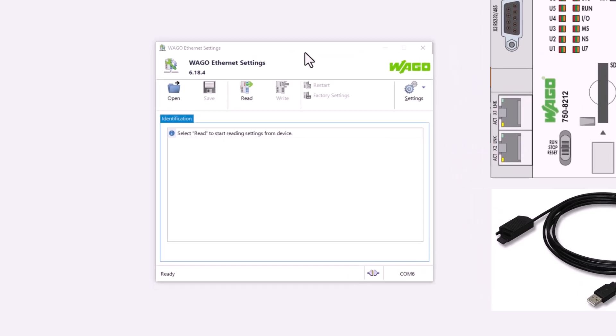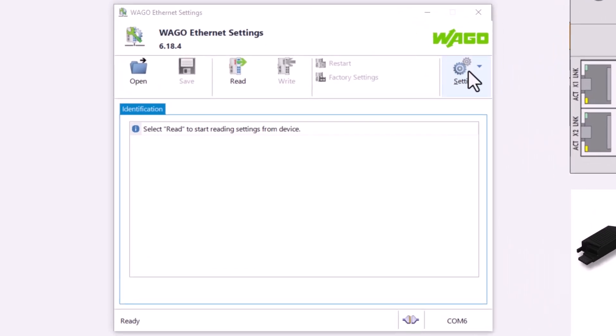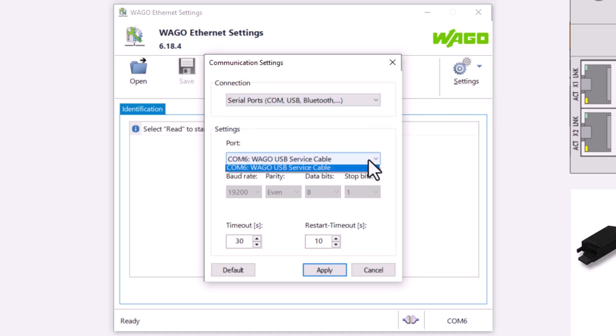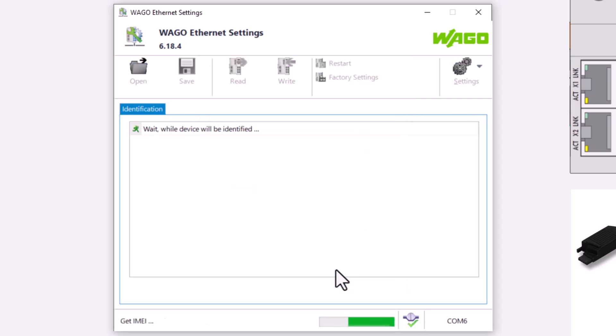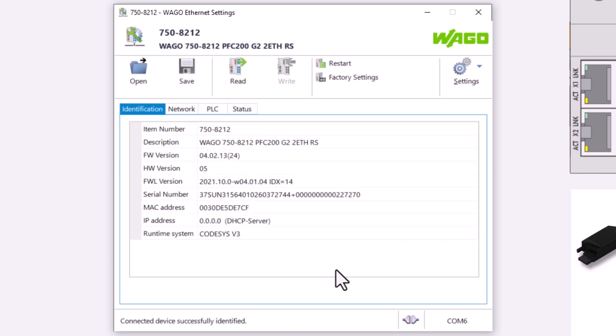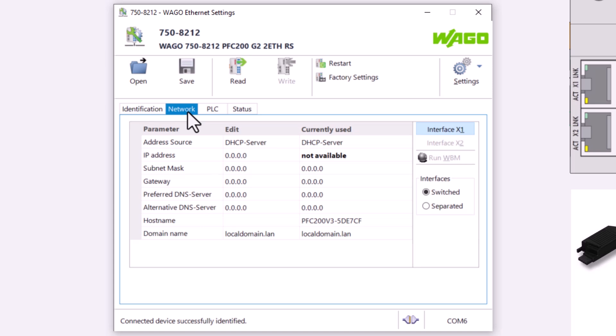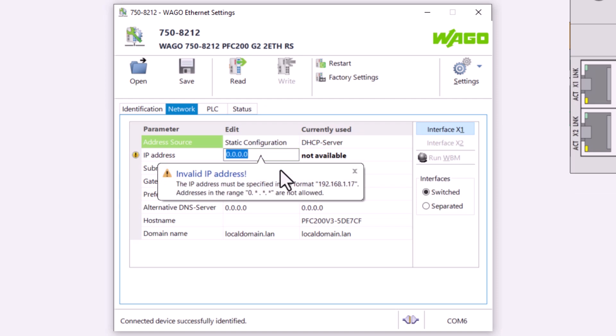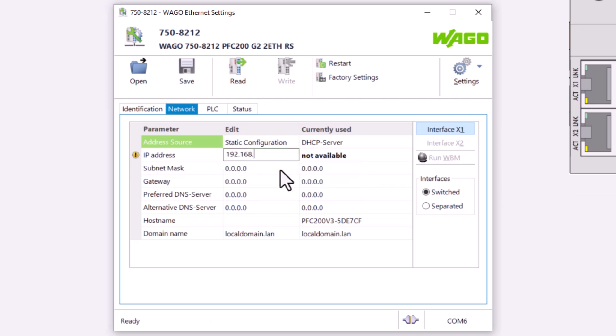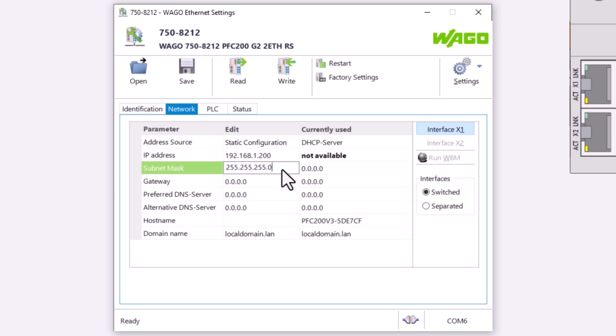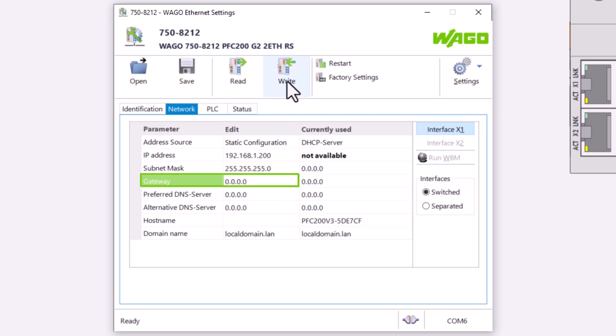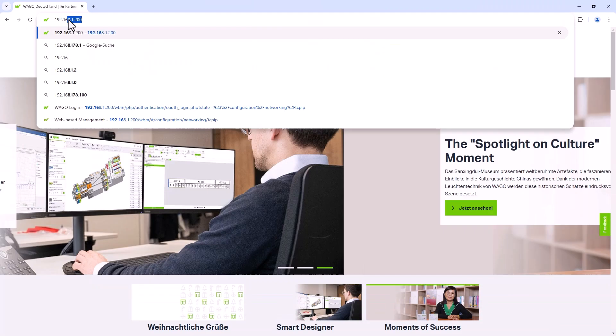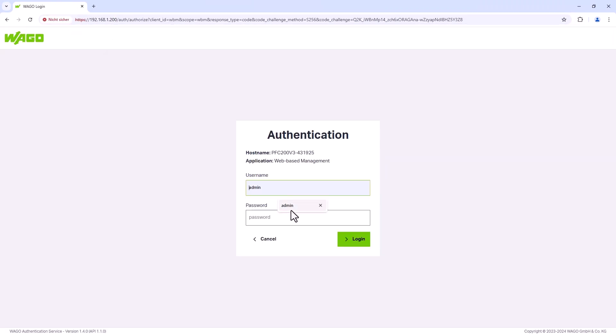In the WAGO Ethernet settings, open the communication window by clicking on the settings button. Under connection, select serial port and then the WAGO USB service cable. Confirm by clicking on apply. The controller is found and we can assign a static IP address in the network tab. The source is still set to DHCP server. We set this to static configuration and enter the desired IP address, a subnet mask, and if necessary a gateway, which we leave blank here. The right button transfers the configuration to the controller, and when we enter the IP address in the web browser, the controller's WBM opens and we are connected.